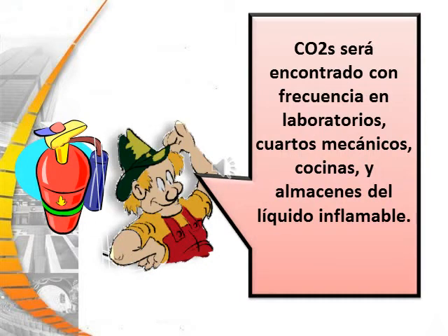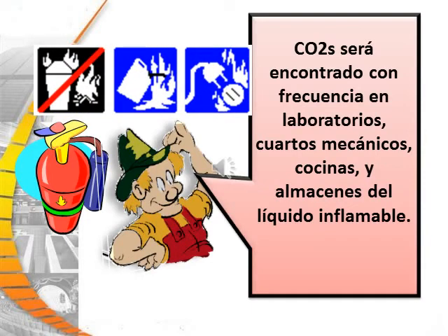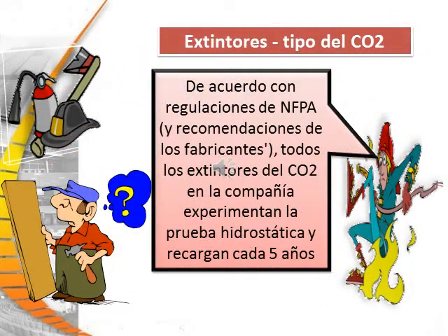CO2s are frequently found in laboratories, mechanical rooms, kitchens, and flammable liquid storage areas. CO2 continued. According to NFPA regulations and manufacturer recommendations, all CO2 extinguishers at a company undergo hydrostatic testing and recharging every 5 years.